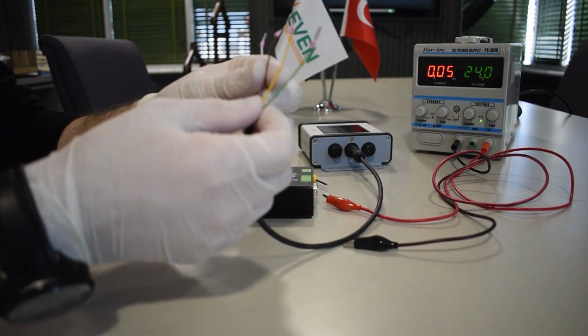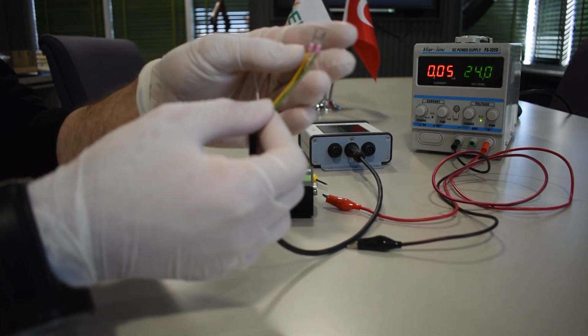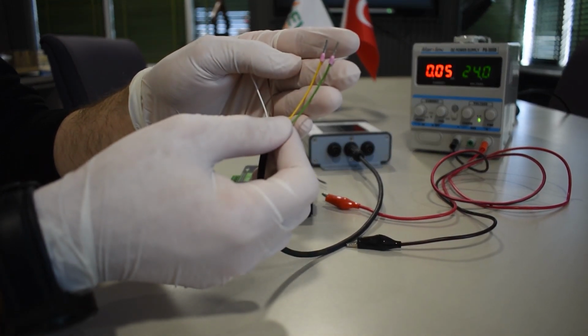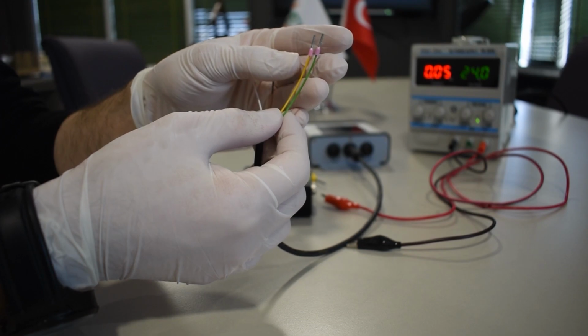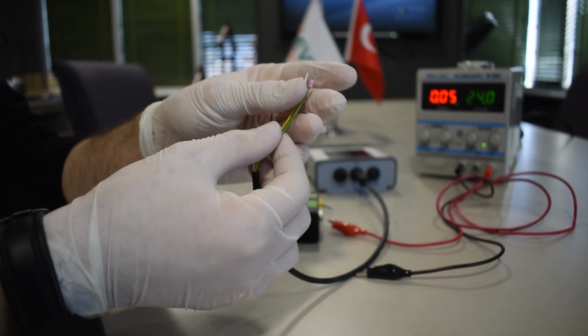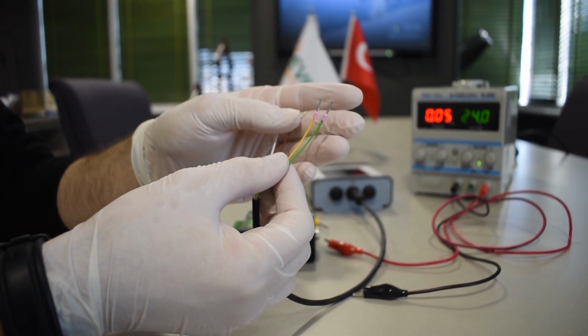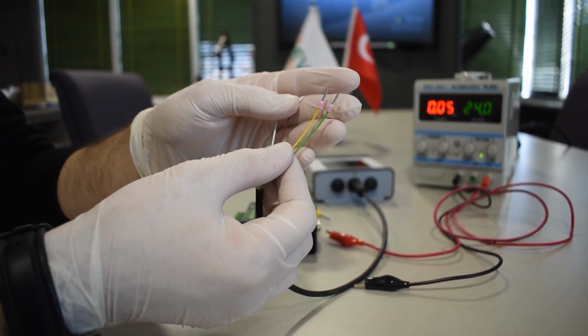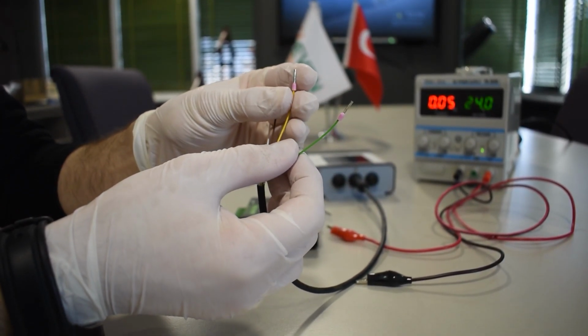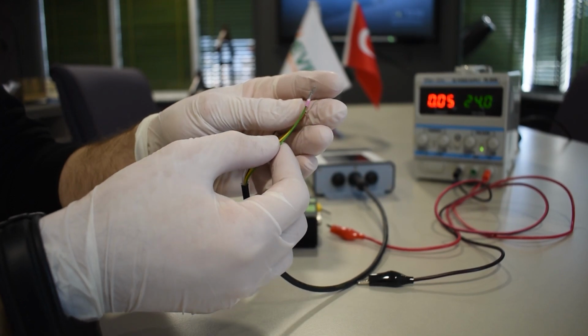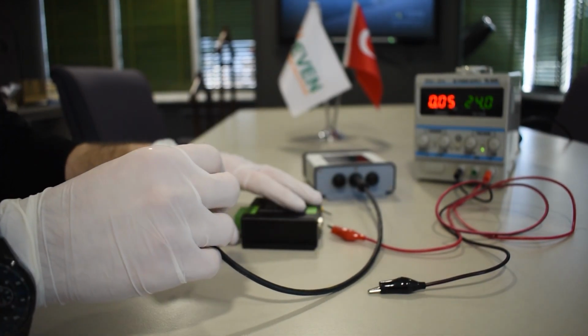Connect the green wire, data plus, of the output cable of the sensor box to the USB RS485 converter data plus, or A. And connect the yellow wire, data minus, of the output cable of the sensor box to the USB RS485 converter data minus, or B.